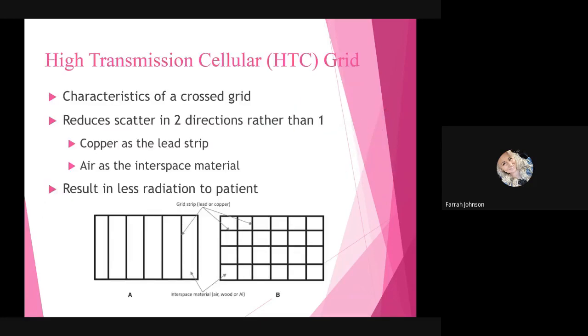Then that brings us to a high transmission cellular, or HTC, grid. These have the characteristics of a crossed grid. They help reduce scatter in two directions rather than one. For the lead strips, they use copper, and for the interspace material, instead of carbon or wood, they use air. And they result in less radiation to the patient. So, for example, in a normal grid, you would just have your strips and then your interspace material in between. With a crossed grid, you're basically creating a picnic basket. Now we have grid lines going horizontally and vertically, which helps to reduce scatter in both directions.